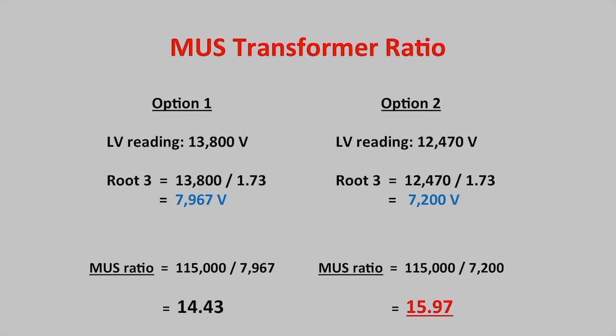Use the neutral position, 115,000 volts, of the high voltage ULTC to determine the MUS calculated ratio. The 13,800 volt option provides a ratio of 14.43. 115,000 divided by 7,967 equals 14.43. The 12,470 volt option provides a ratio of 15.97.